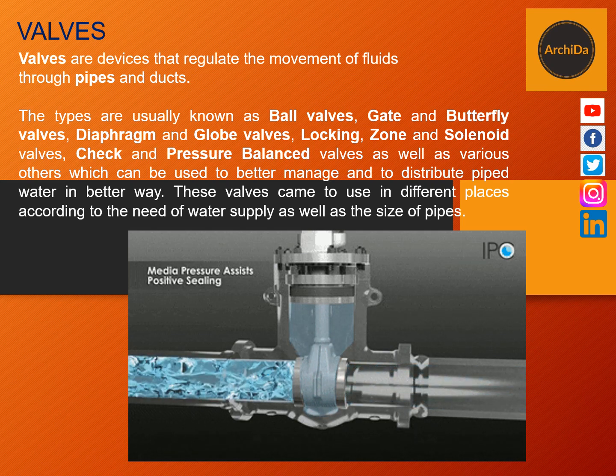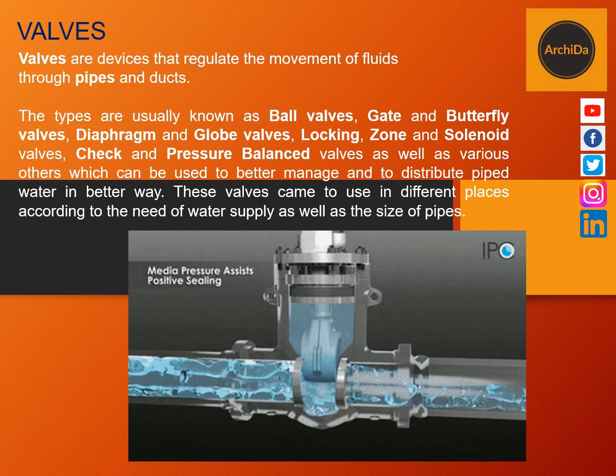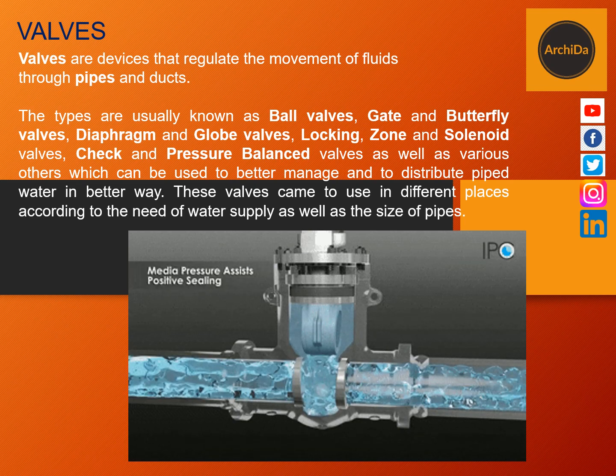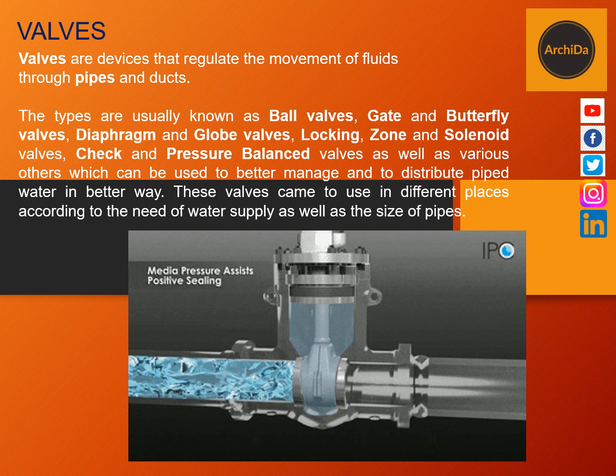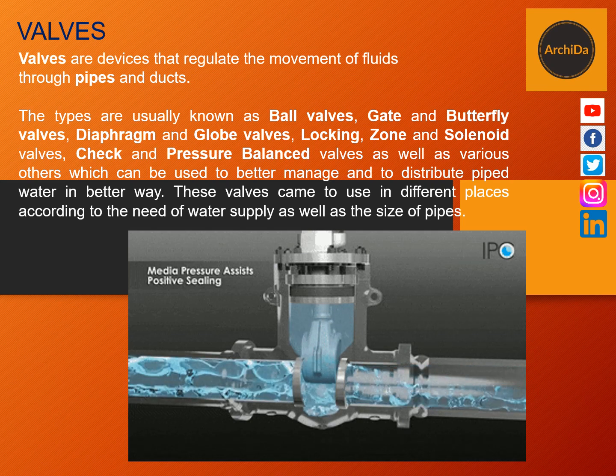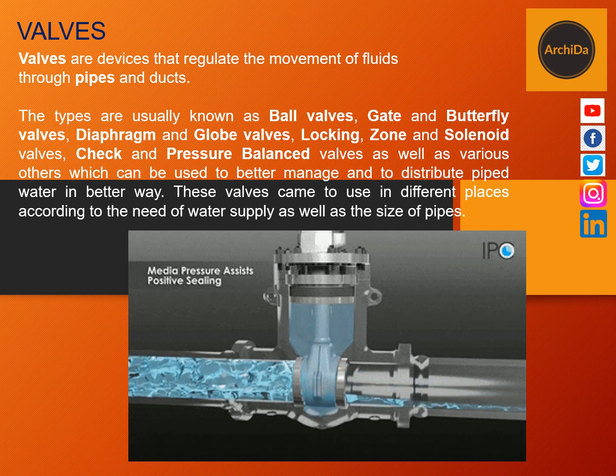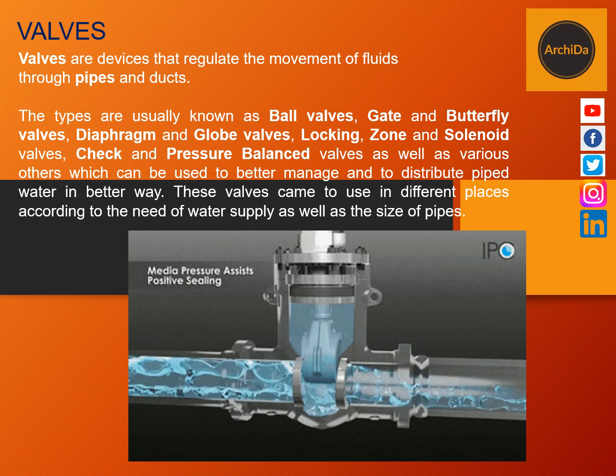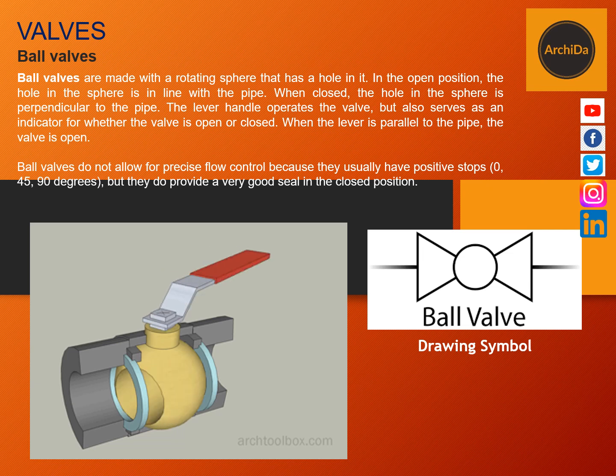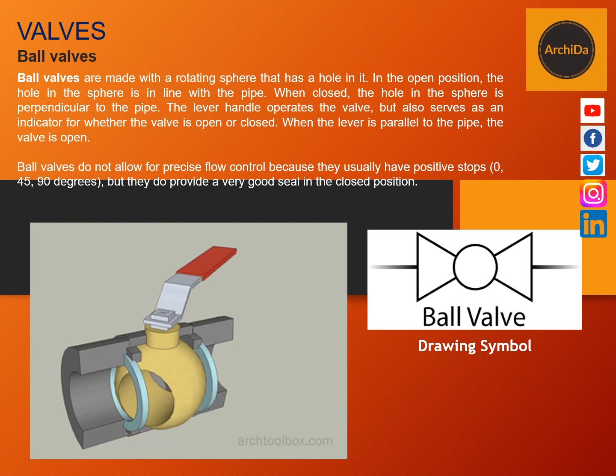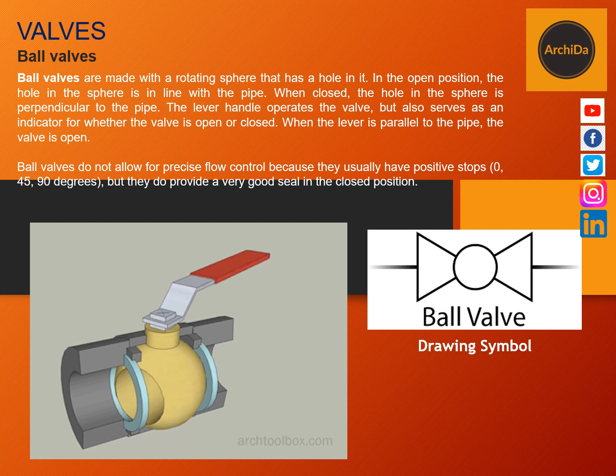The next part of a hot and cold water system are called valves. Valves are devices that regulate the movement of fluids through the pipes. The types are usually known as ball valves, gate and butterfly valves, diaphragm and globe valves, locking valves, zone and solenoid valves, and check and pressure balance valves. Ball valves are made with a rotating sphere that has a hole in it. In the open position, the hole in the sphere is in line with the pipe. When closed, the hole is perpendicular to the pipe, thus preventing the water from flowing.